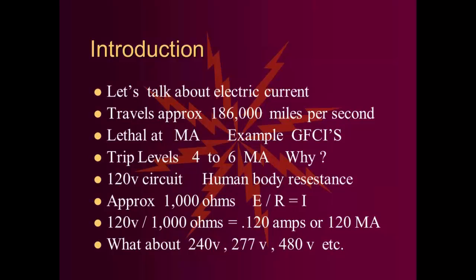Why? Well, let's take a look at it. You have a 120 volt circuit. The human body has a resistance of approximately 1,000 ohms. So to see the relationship, we have the voltage, which is E, divided by the resistance, which is R, which would then give us the current flow. At the bottom of the screen, we see 120 volts divided by 1,000 ohms is 0.120 amps or 120 milliamps. And you might say, okay, so what? Well, look at what the damage level is. 4 to 6, you're at 120. That's 20 times the amount of current that the human body can withstand. 20 times. Now, if you do the same thing with 240 volt, 277 volt, 480 volt, etc., you begin to get the idea as to what we're talking about.